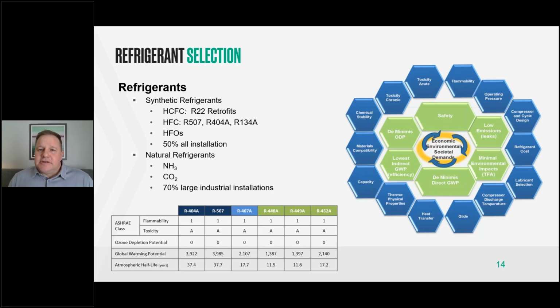In terms of that selection, if we look at historical data, HFCs and HFOs have moved and started being in about 50% of the installations. Then you've got ammonia, which has been kind of a niche market for larger industrial type applications, but has its challenges: one, it's flammable; two, it's toxic. So it's not usable in a lot of applications in this market. CO2 is the newest, meaning about 15 years new, but it's been around for a while. We're moving towards that and using more controls, making it more viable and broader use across the business. It's used in larger installations, but we're tailoring it to smaller fixed systems.